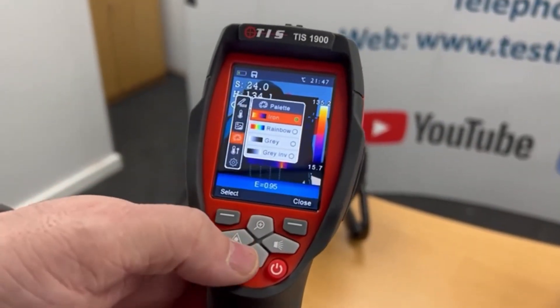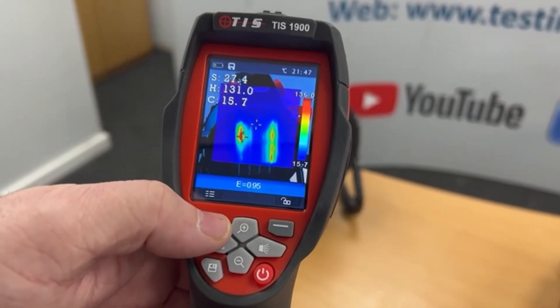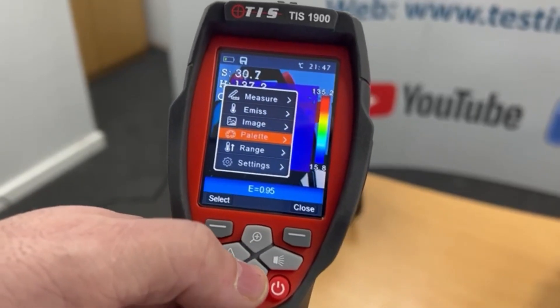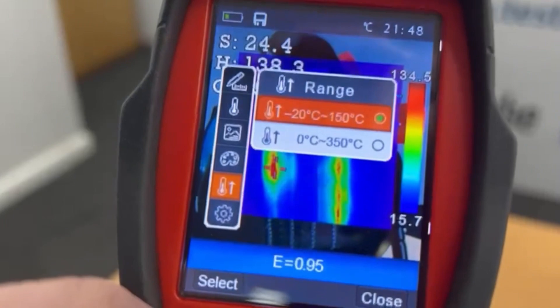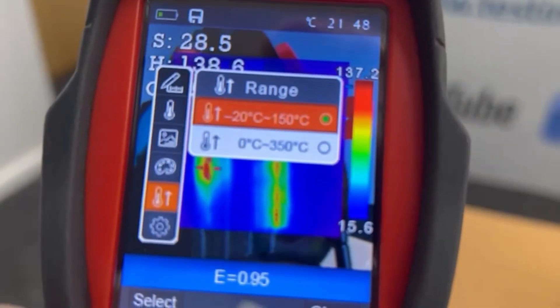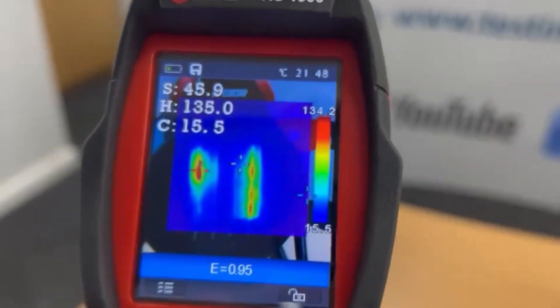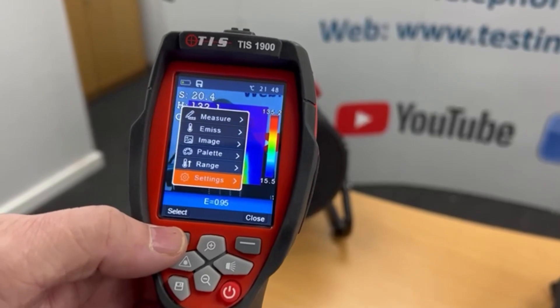I can also change the palette — it's set to iron, but I can go to rainbow so the hot spots become red and the cold spots become blue. You can also change the temperature range, so you can go minus 20 to 150 or 0 to 350 degrees, and you can change date and time and various other settings in there as well.